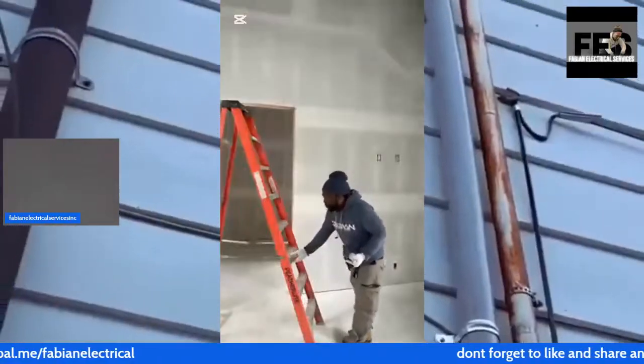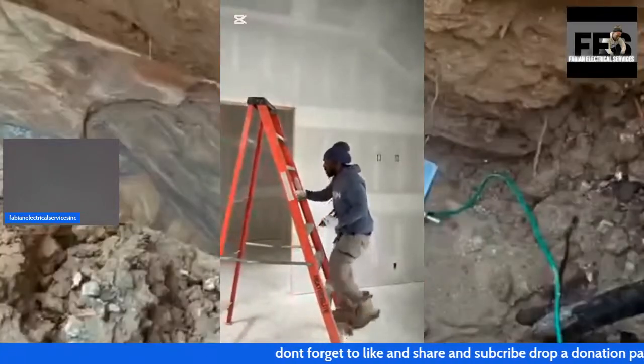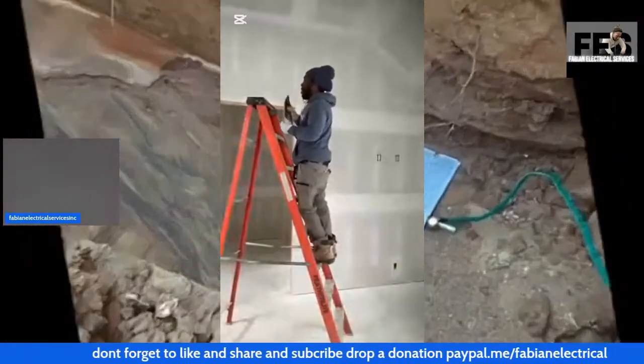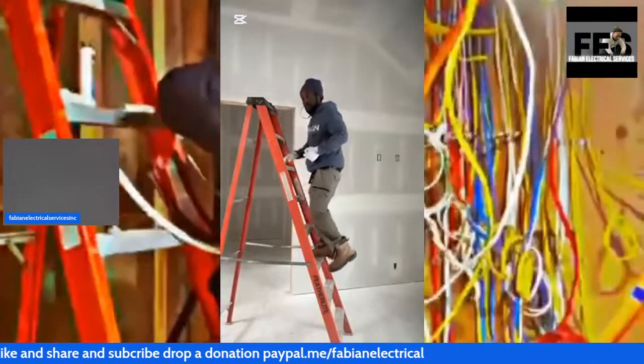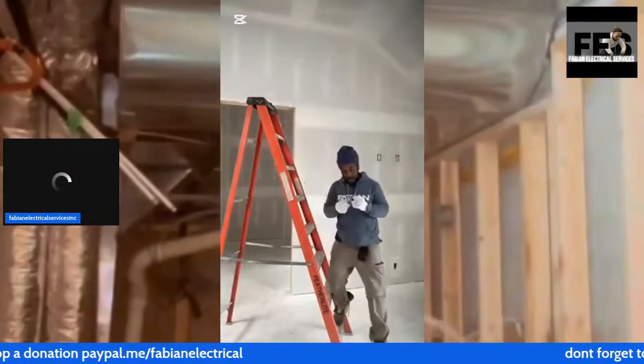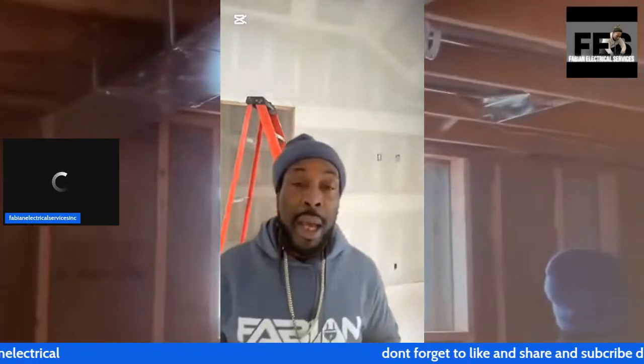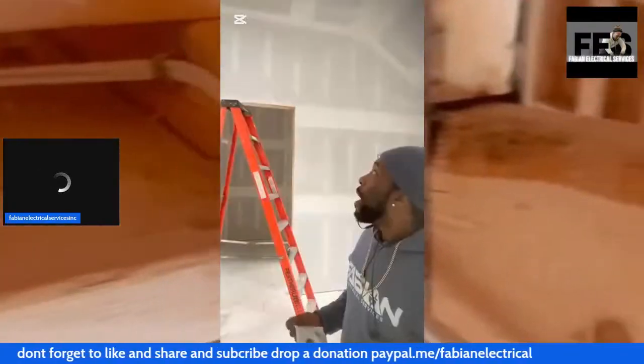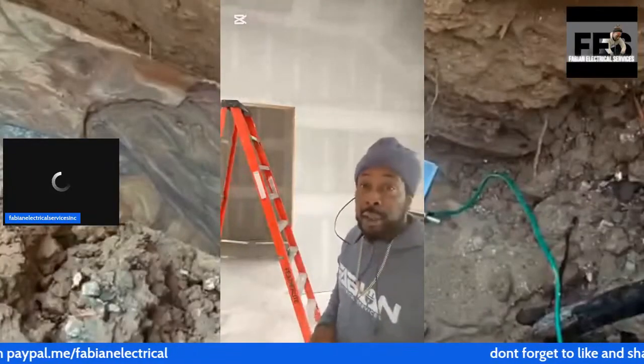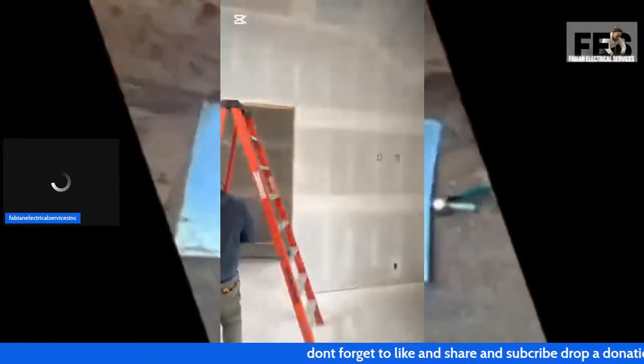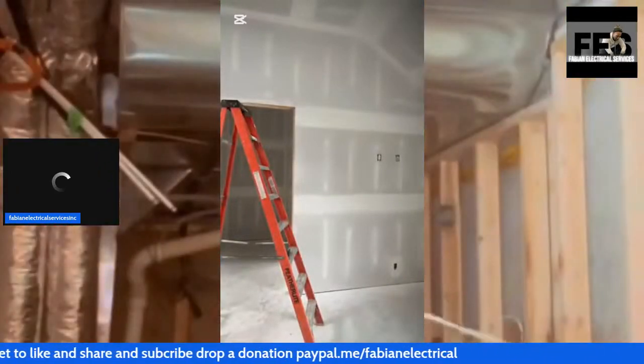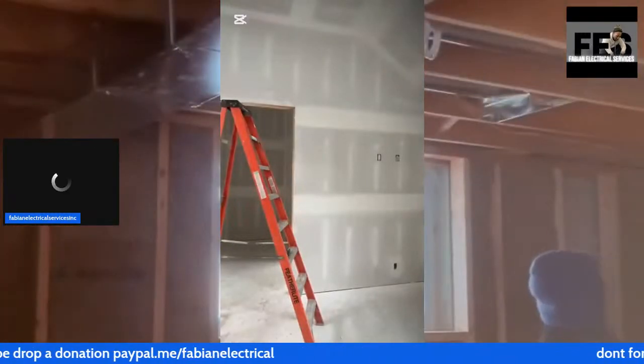It's also very important to remember that once you finish your electrical installation for the lighting and smoke detectors, make sure you label the panel with the smoke and lighting combined. That's one requirement the inspector is going to want to see at the panel, labeled in that manner. Rather than troubleshooting at the end of the job, because troubleshooting takes a lot of time that we don't actually need to waste, I like to label my wires before I even walk away from the panel.